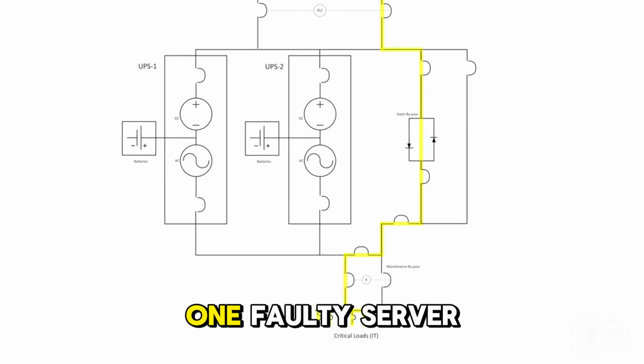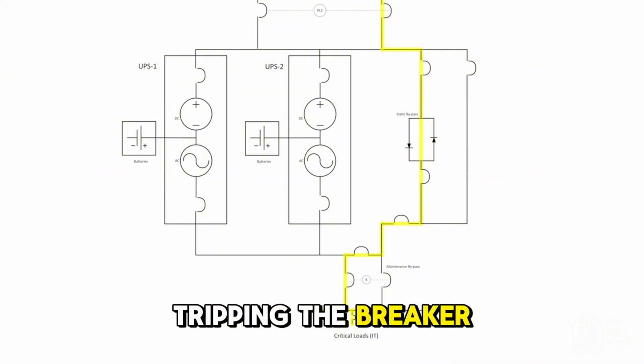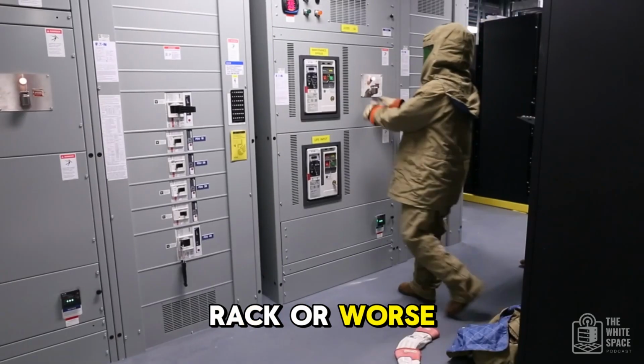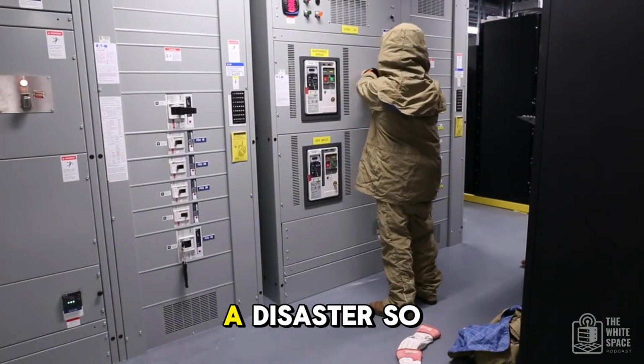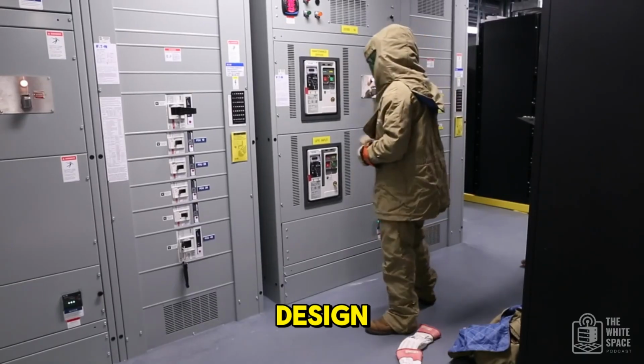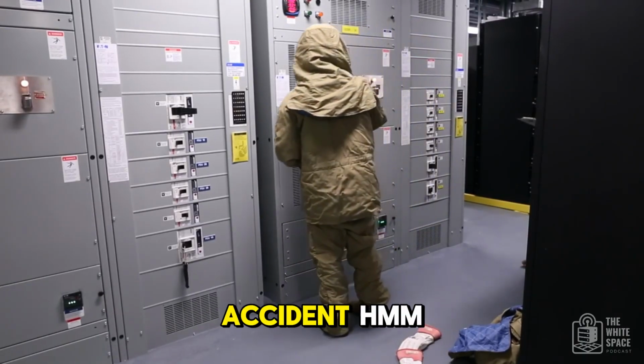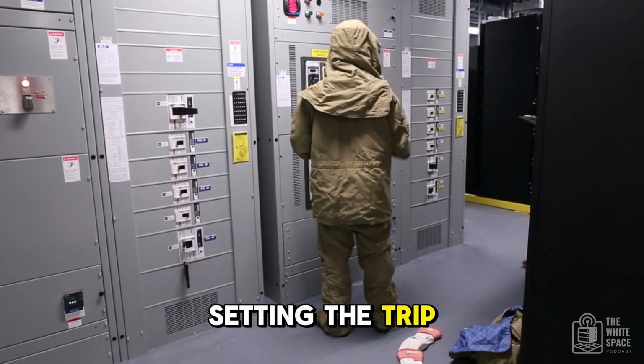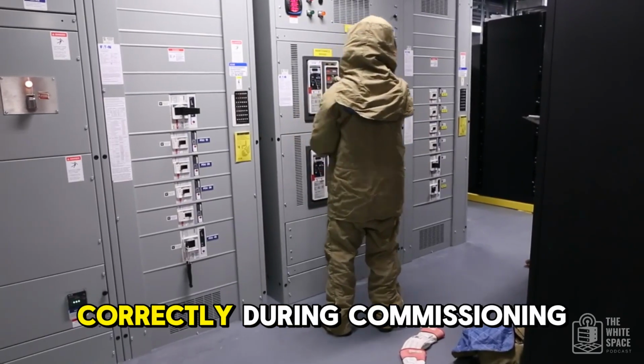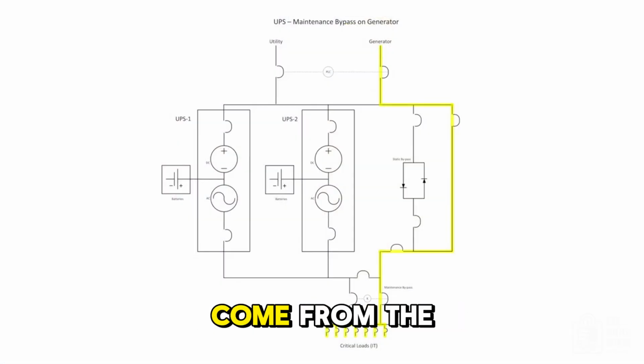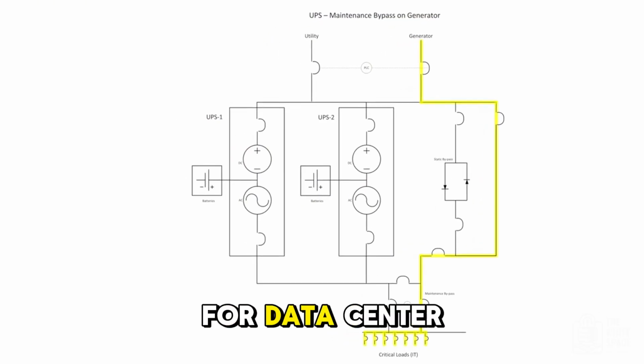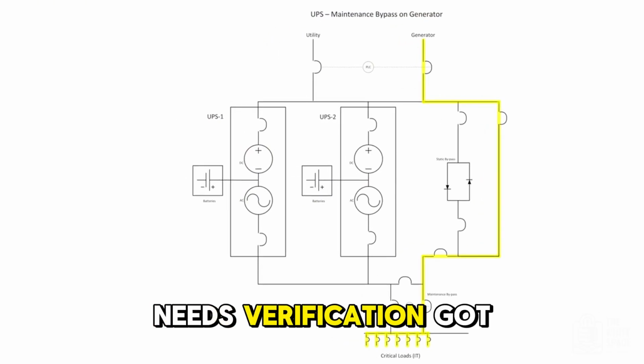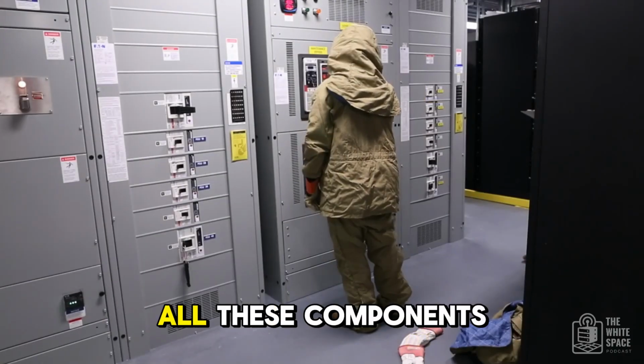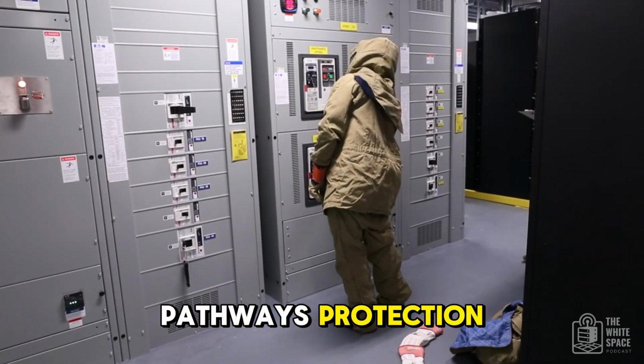Exactly. You don't want one faulty server tripping the breaker for an entire rack, or worse, a whole section of the data center. That would be a disaster. So this needs careful design. Has to be designed in from the start. It's not an accident. And it also means setting the trip characteristics of the breakers correctly during commissioning. They don't always come from the factory set up perfectly for data center loads. Needs verification. Got it.